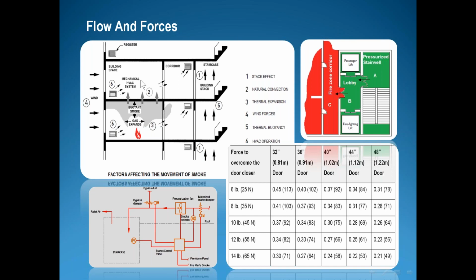So to be an airlock, if you enter here, then this door will close, and you can open this and go, so it will be balanced here, okay? Or you can, as in this figure, extract from the top point of the corridor, but don't forget, in any smoke management system, to add the makeup air.